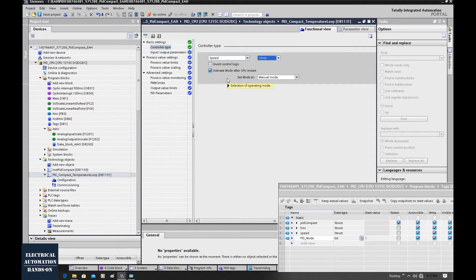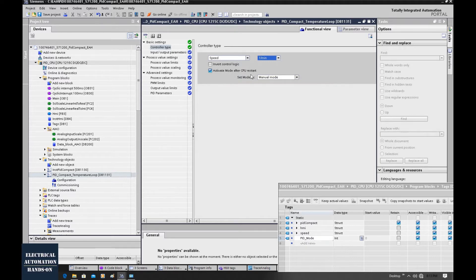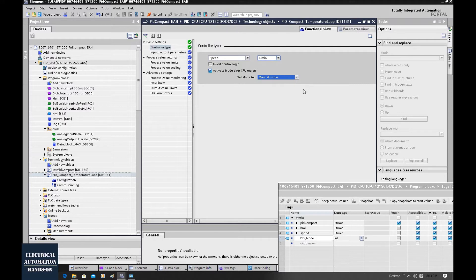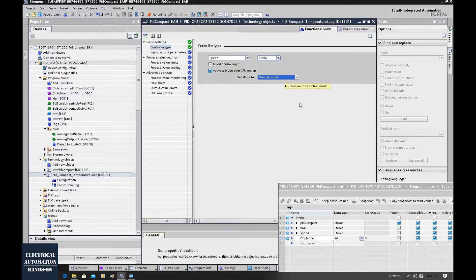The next selection is also important, though usually we can leave it as default. By default, if the CPU gets a restart while in control mode, it will switch to manual mode. That's what we want in most cases, because after a CPU restart we want to keep the system in a safe mode — which is manual mode.